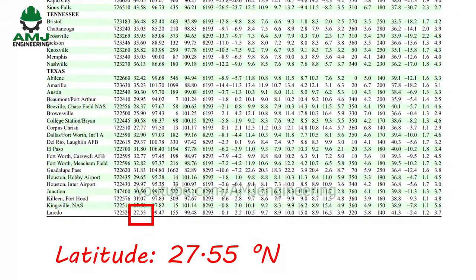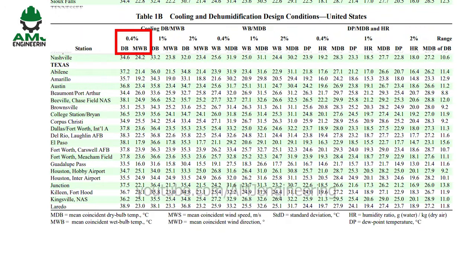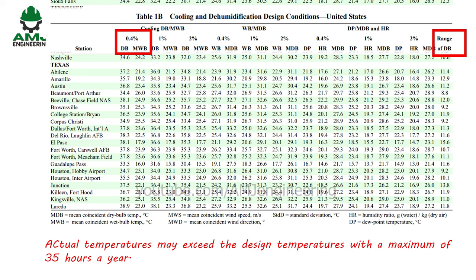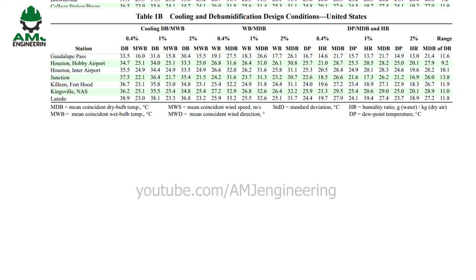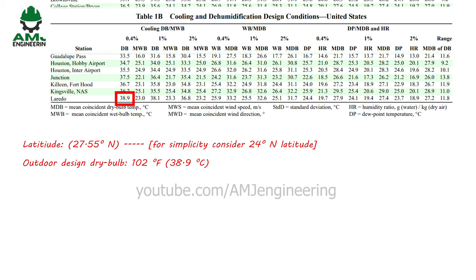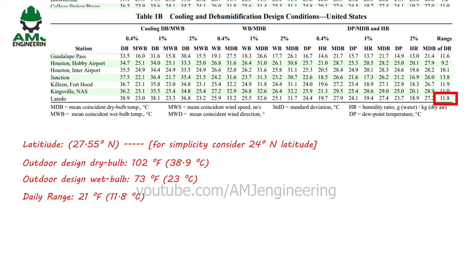From Table 1A we find the latitude. From Table 1B we take the 0.4% dry bulb, mean coincident wet bulb, and daily range of dry bulb. The 0.4% summer design condition means temperatures will exceed this value only about 0.4% of the time — less than 35 hours per year — avoiding oversizing the system. From these tables: latitude 27.55°N (simplified to 24°N); outdoor design dry bulb 102°F; outdoor design wet bulb 73°F; daily range 21°F.